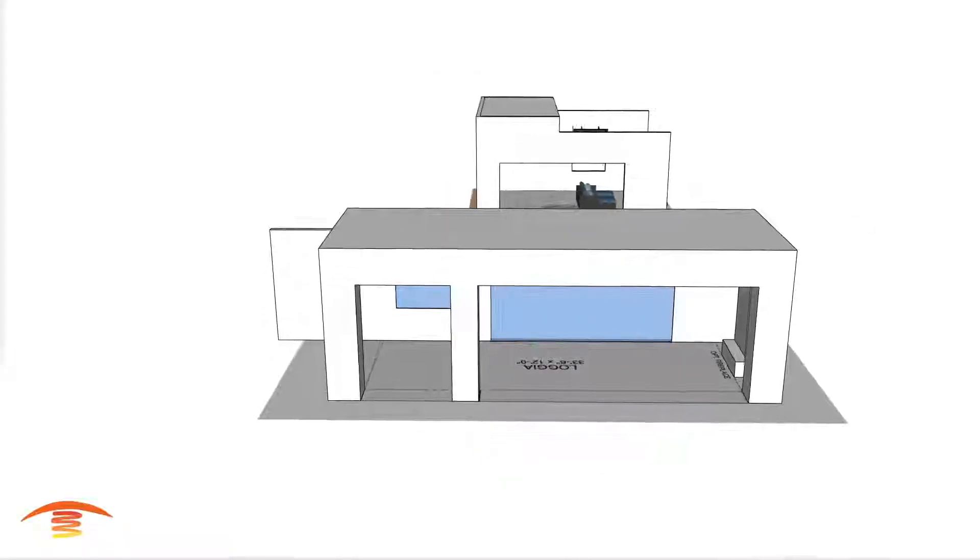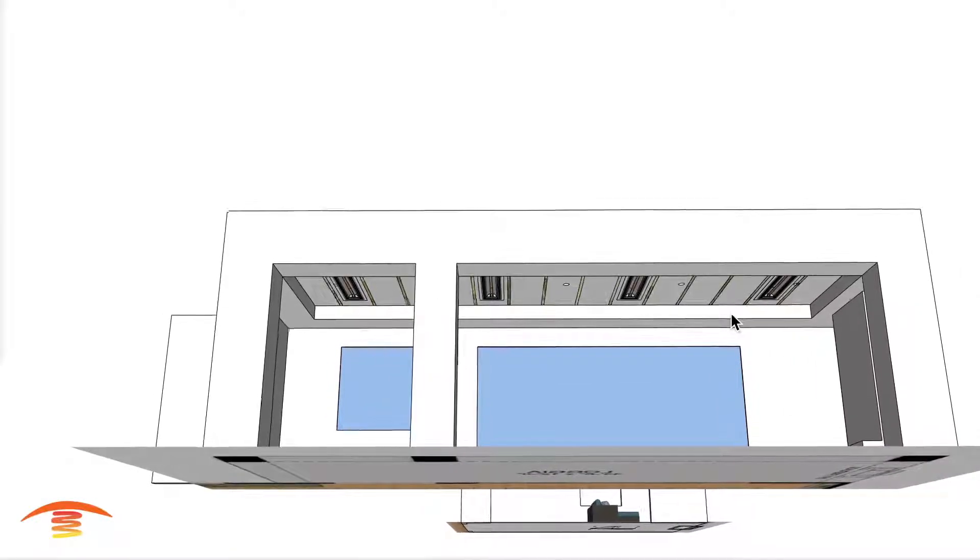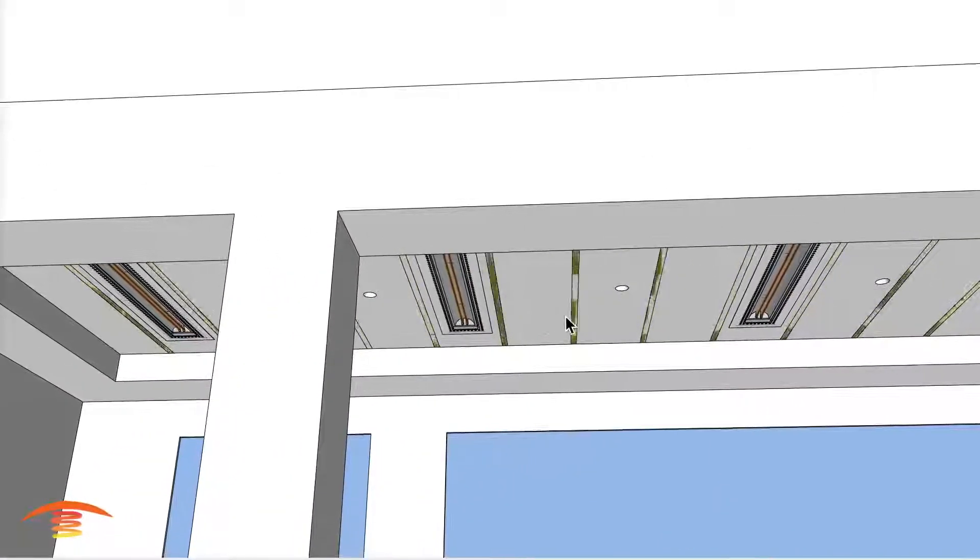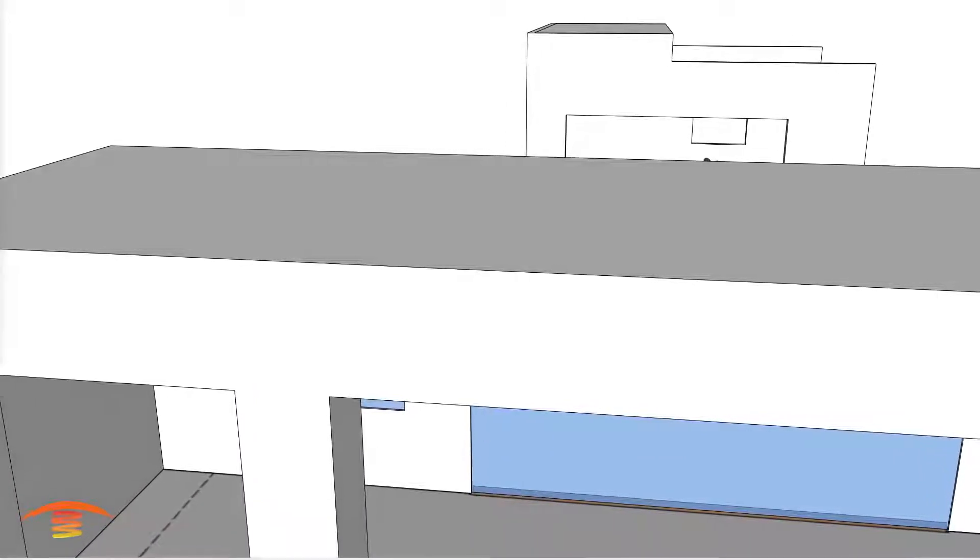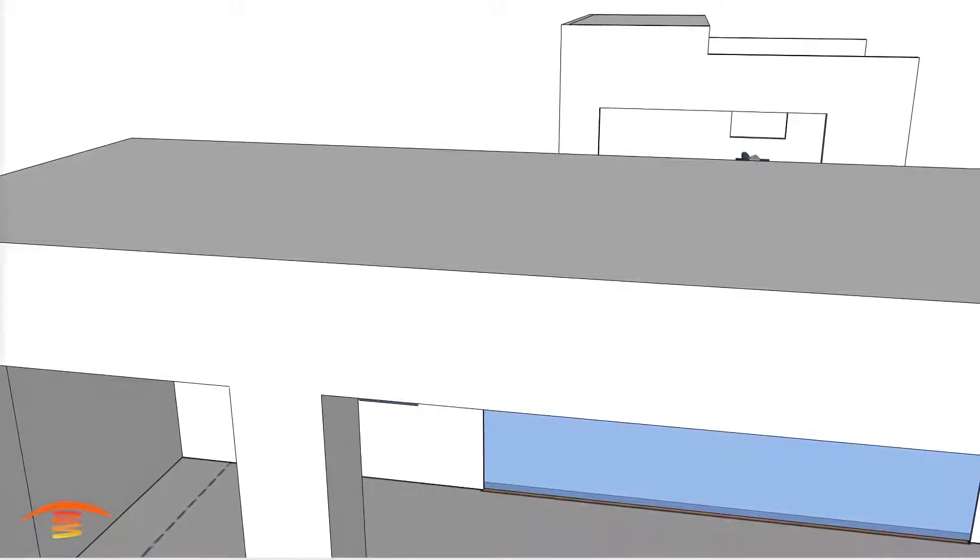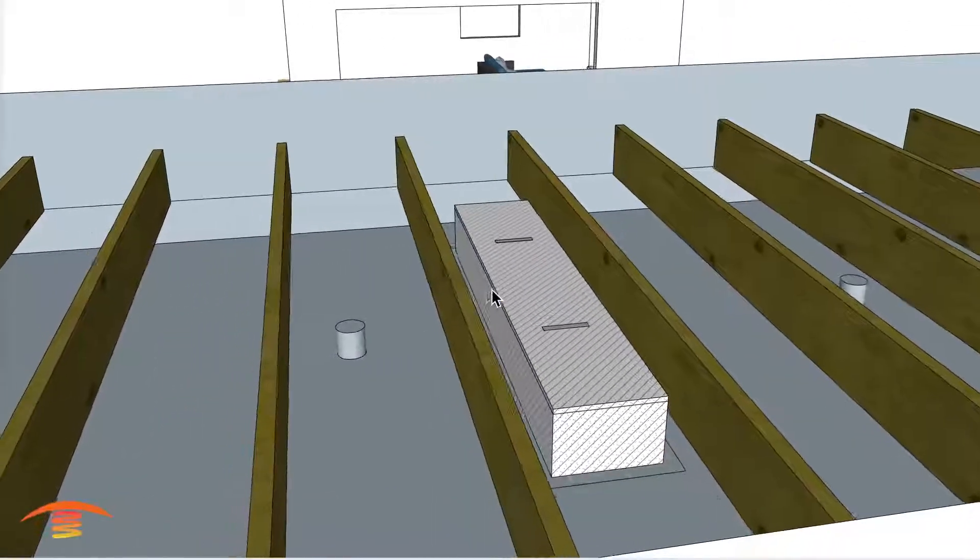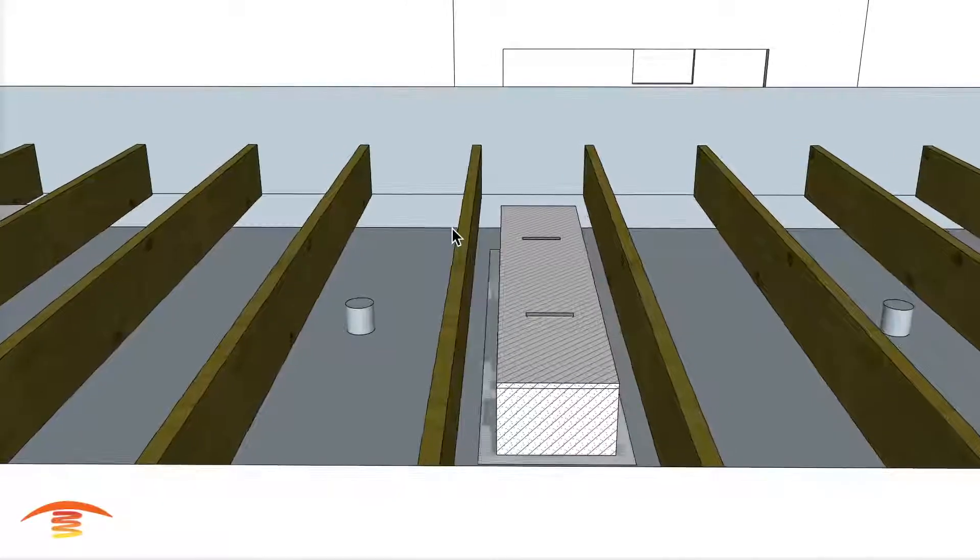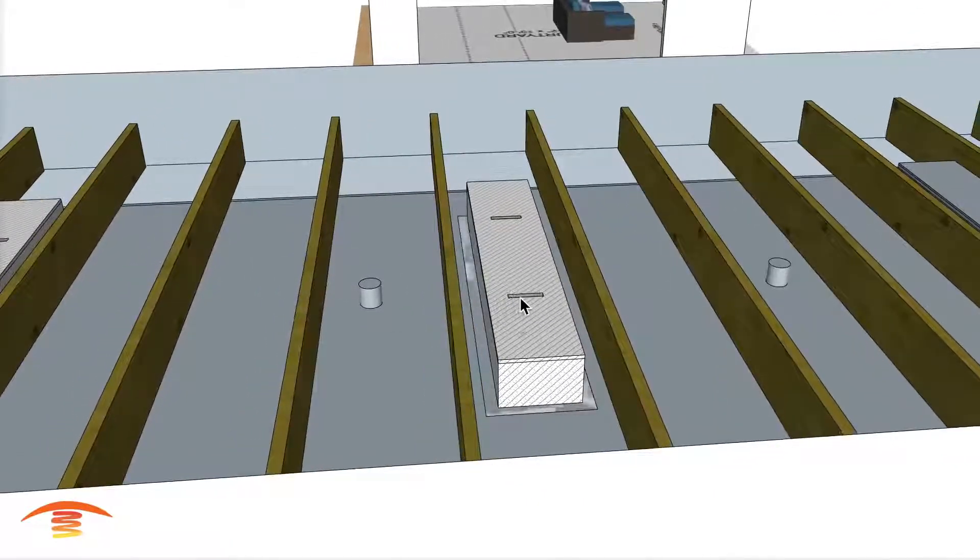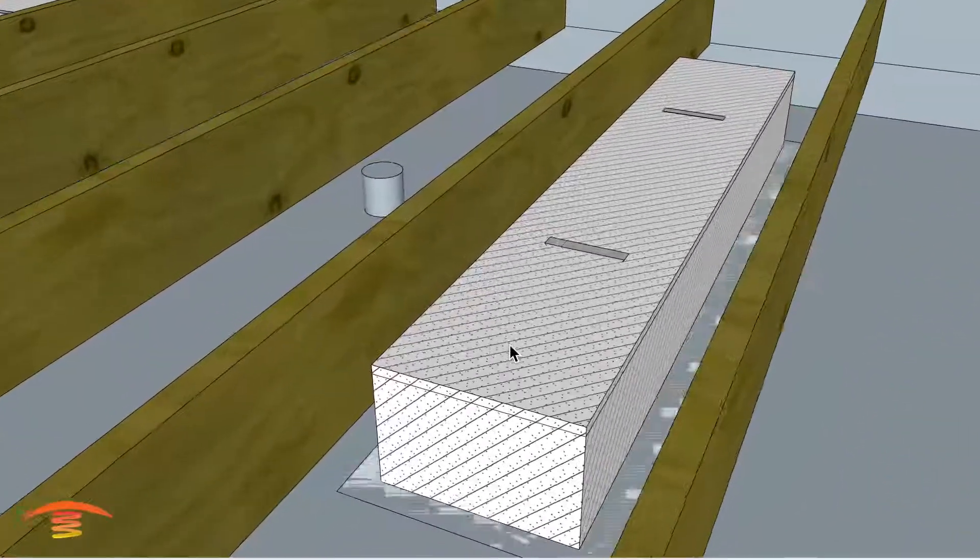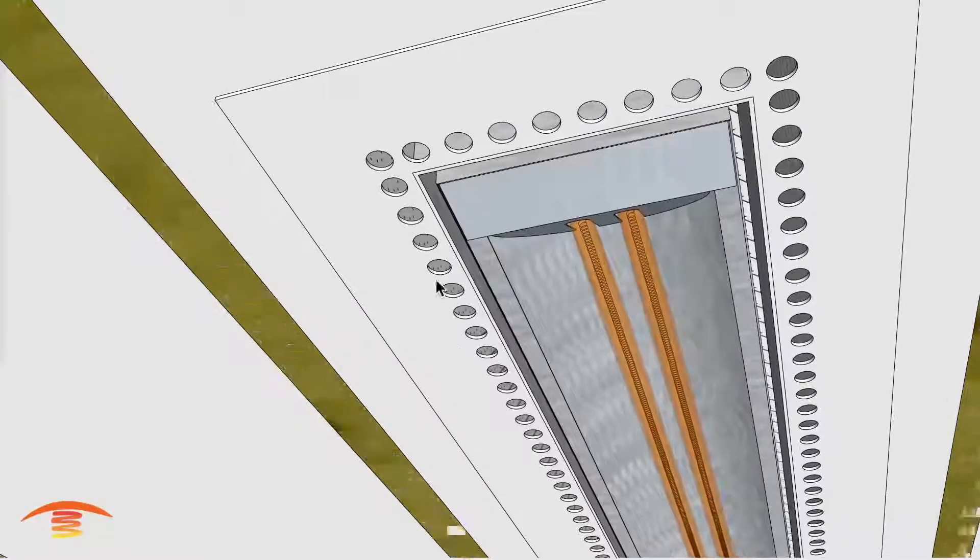So you might have noticed already that I've placed four 6,000 watt units in a flush mount kit. One of the issues that we might have is the location of the trusses or wooden beams up here. The customer did say they were 11 and 7/8ths. I'm guessing these are probably 11 7/8ths by 2. So I do have them on 24 inch centers. There's plenty of room between that for placement of a flush mount kit. Here you'll see the kit. This is not the complete kit. What you have is the flush mount frame and then you have the heater itself.